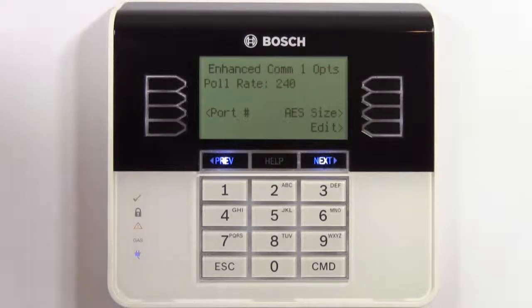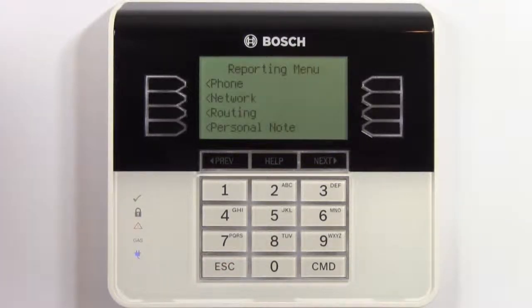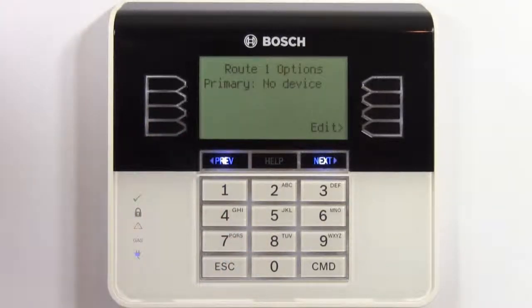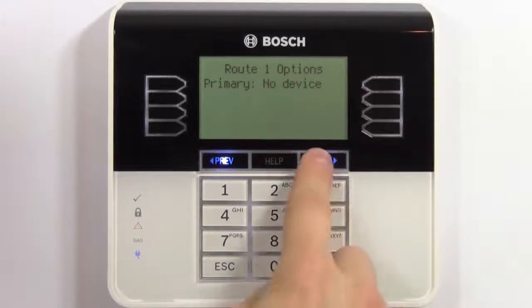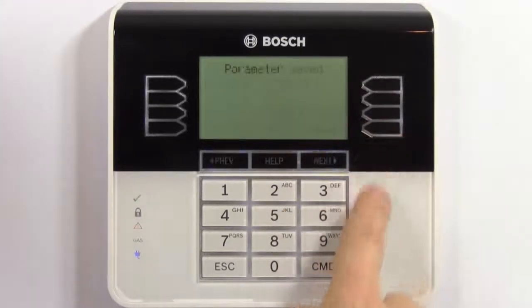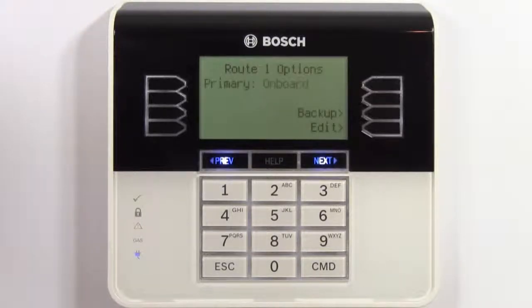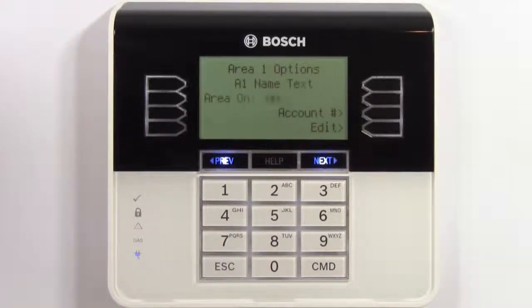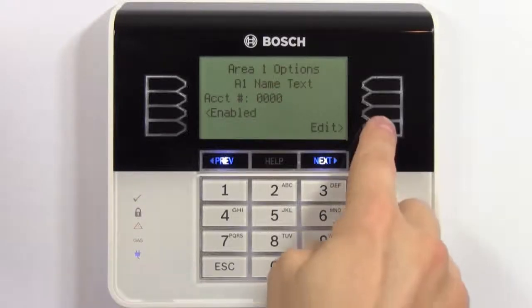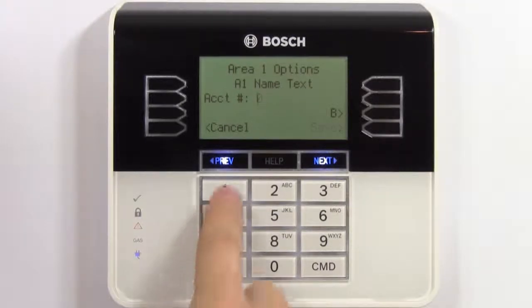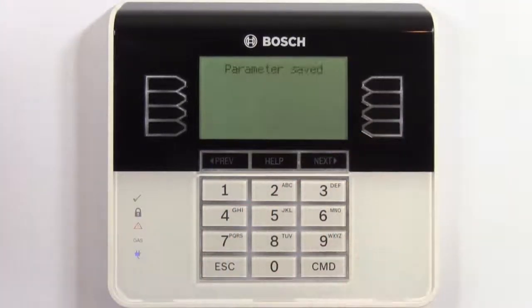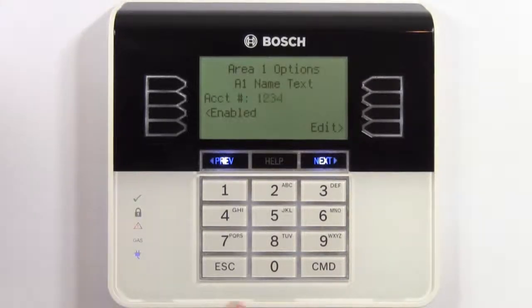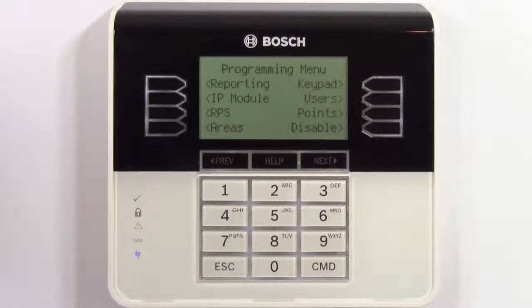Escape back to the reporting menu and select routing. Select edit to edit the primary device and press the next button to select onboard 1. After that is saved, press escape again back to the programming menu. Now select areas, browse to the account number, and enter your area 1 account number.